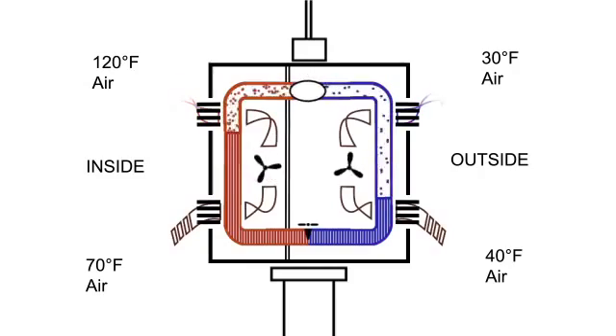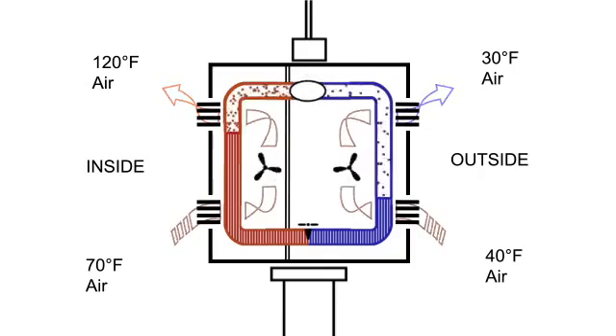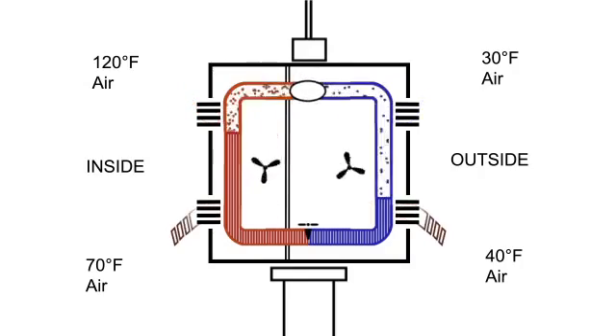In a heat pump, we simply reverse the flow in the winter when we want heat. By switching the direction of the coolant, the cold side, the evaporator, flips to the outside of the building, and the warm side, the condenser, moves to the inside.